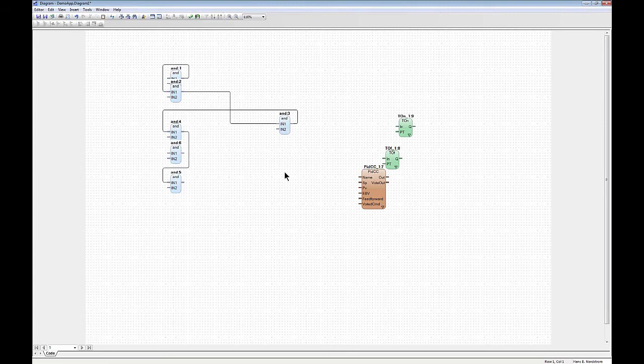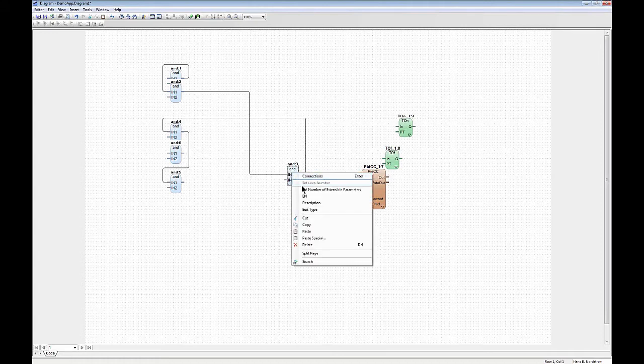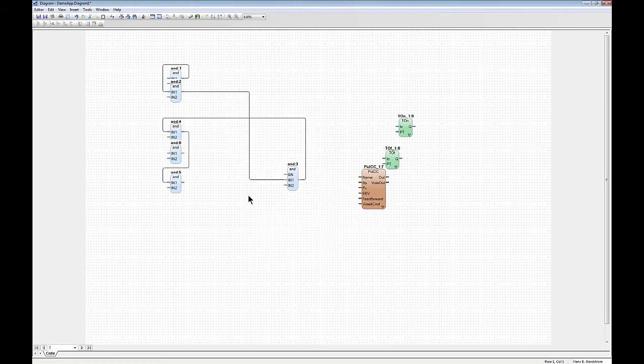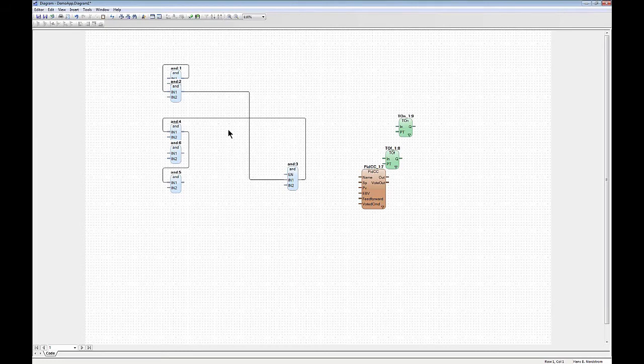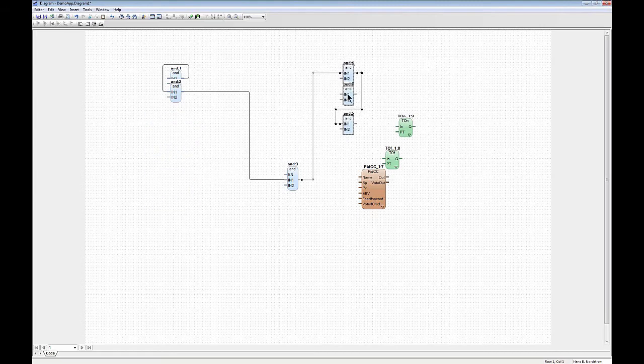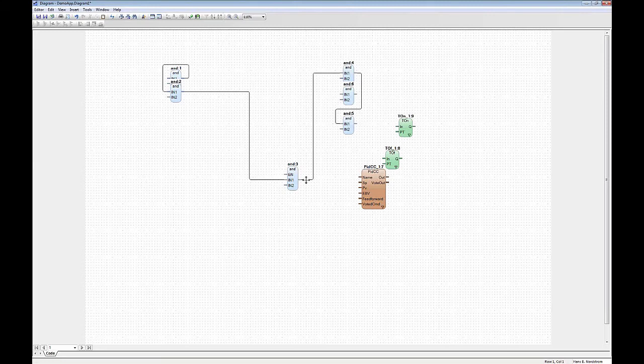Sometimes there is a need for conditional execution of a block — either because you actually want it that way, or for debugging purposes. You can mark the block, right-click, and say 'give me an EN port'. The EN port means the block will only be executed when the EN port value is true — it's like an if statement in structured text. When EN goes false, the block won't execute and its output will be frozen, which can be very useful when debugging complex logic.